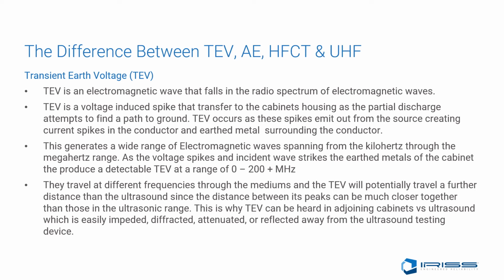This generates a wide range of electromagnetic waves spanning from the kilohertz through the megahertz range. As the voltage spikes and incident waves strike the earthed metal of the cabinet, they produce a detectable TEV at a range of 0 to 200 megahertz. They travel at different frequencies through these mediums, and the TEV will potentially travel at a further distance than ultrasound since the distance between its peaks can be much closer together than those in the ultrasonic range. This is why TEV can be heard in adjoining cabinets versus ultrasound, which is easily impeded, diffracted, attenuated, or reflected away from the ultrasound testing device.